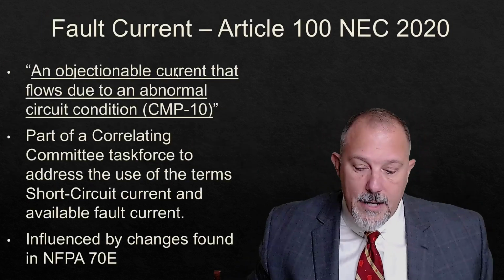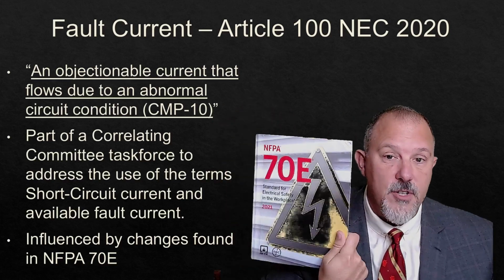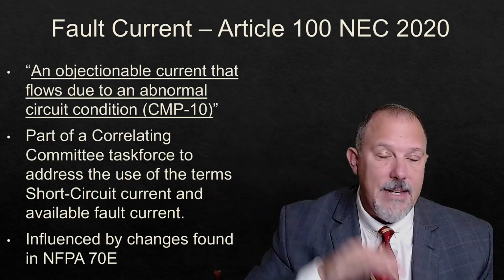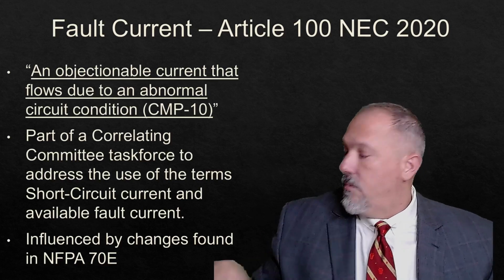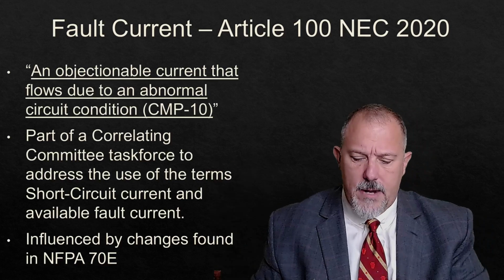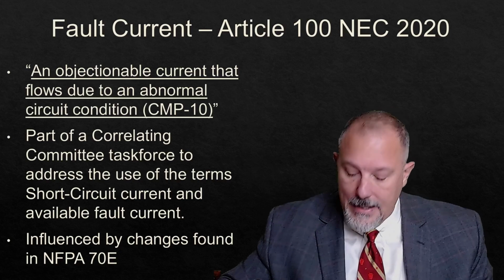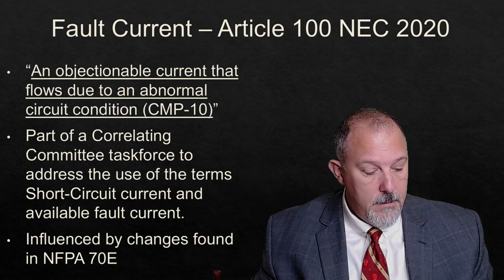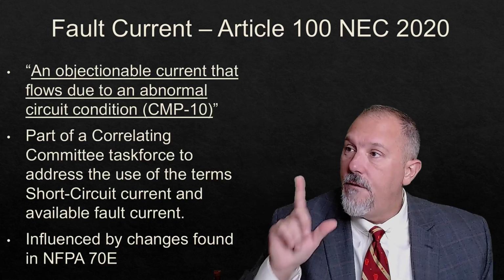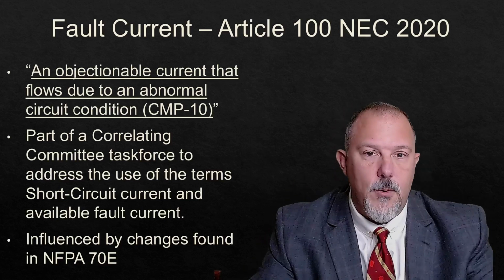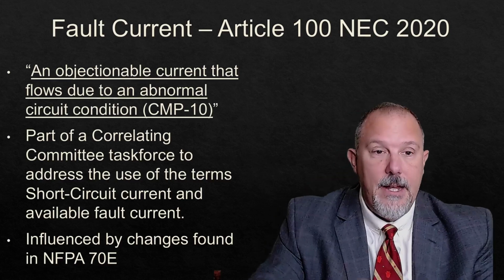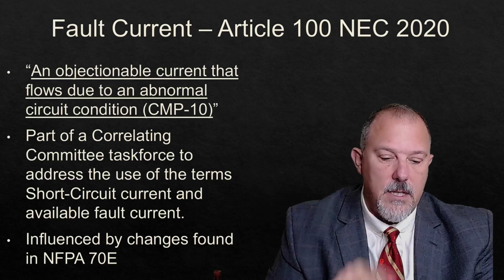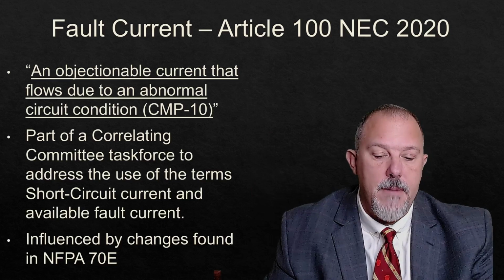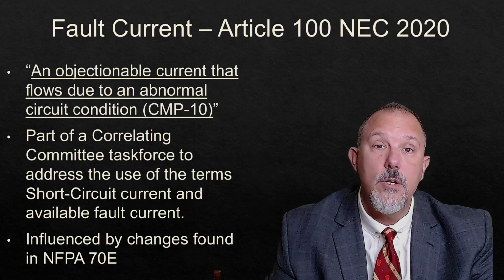Fault current, Article 100, NEC 2020, which again, remember, it started in 70E. Is the definition exactly the same? Let's take a look. I'm going to grab 70E and read what's in it, and all of you can take a look and say, is it the same? 70E says, fault current: the amount of current delivered at a point on the system during a short circuit condition. Ooh, look, it's a little bit different.